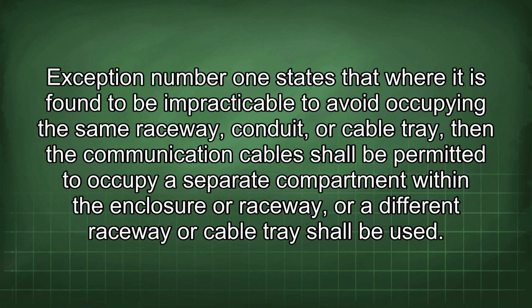Exception number 1 states that where it is found to be impracticable to avoid occupying the same raceway, conduit, or cable tray, then the communication cable shall be permitted to occupy a separate compartment within the enclosure or raceway, or a different raceway or cable tray shall be used.